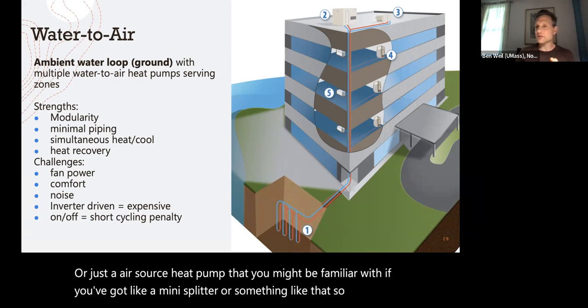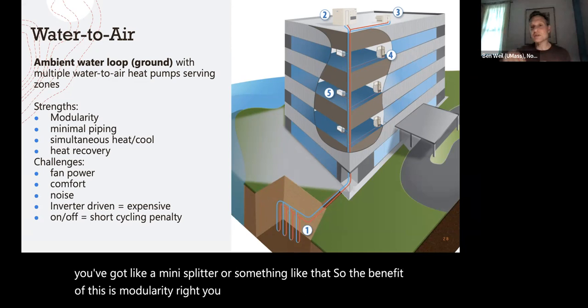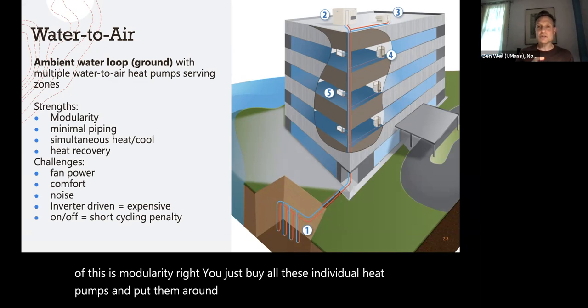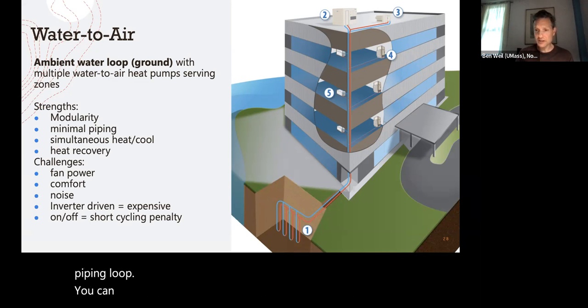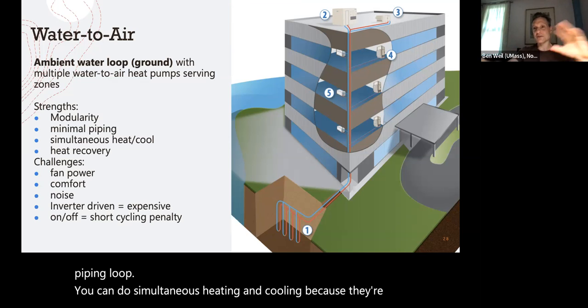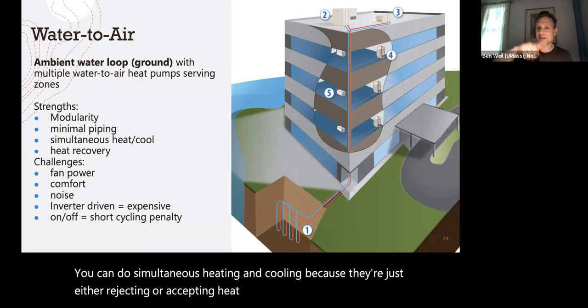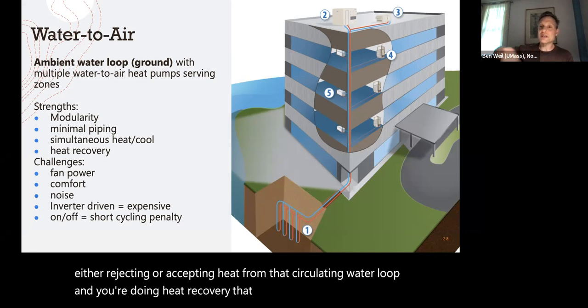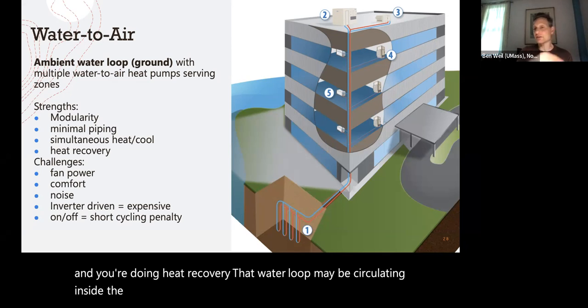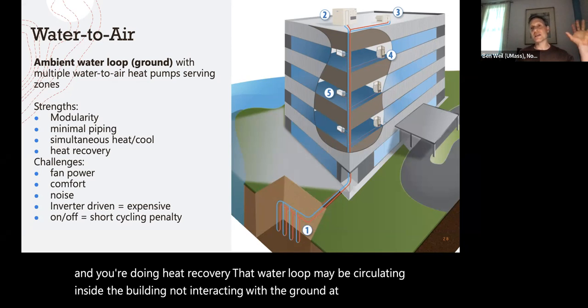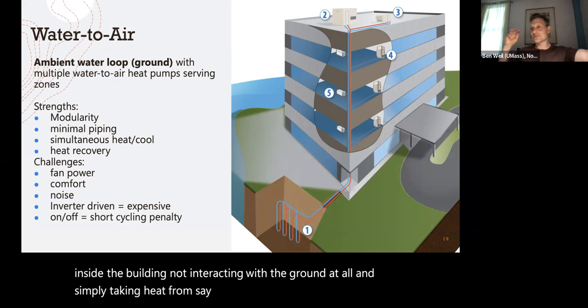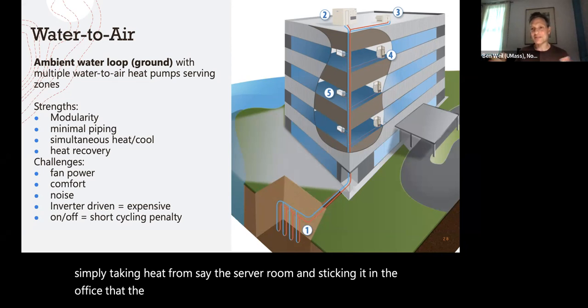So the benefit of this is modularity, right? You just buy all these individual heat pumps and put them around your building. You only have the one piping loop. You can do simultaneous heating and cooling because they're just either rejecting or accepting heat from that circulating water loop. And you're doing heat recovery. That water loop may be circulating inside the building, not interacting with the ground at all, and simply taking heat from, say, the server room and sticking it in the office, the corner office or whatever. And so it's just moving heat around that way.